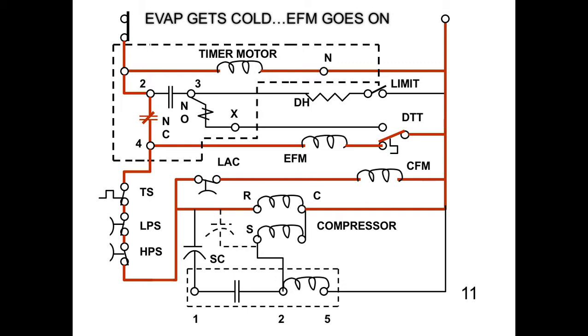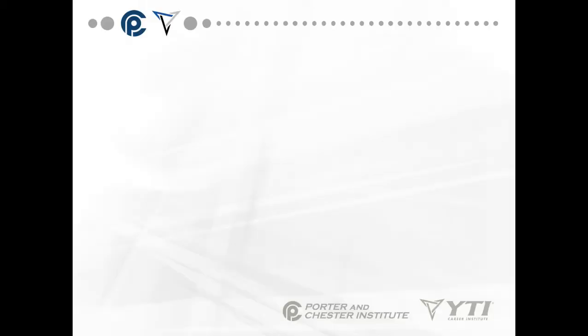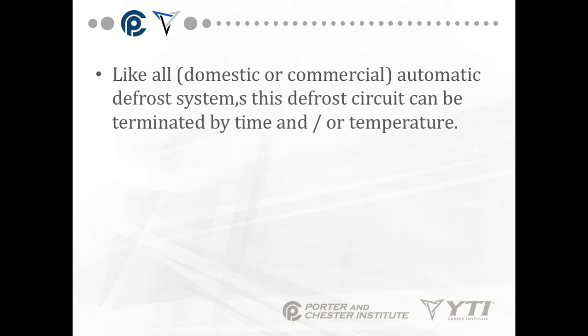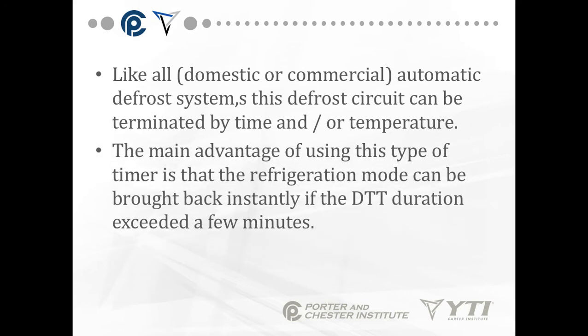The evaporator gets cold. The EFM comes back on. Notice my temperature is dropped. This is temperature because you see the little box-shaped line under it. Temperature is dropped. DTT has moved back down to complete the circuit from pin 4 to the evaporator fan back to line 2 or neutral. DTT is switched into the down position. So like all domestic and commercial automatic defrost circuits, this defrost can be terminated by time and or temperature. The main advantage of this is that the refrigeration mode can be brought back instantaneously if the DTT duration exceeded a few minutes.